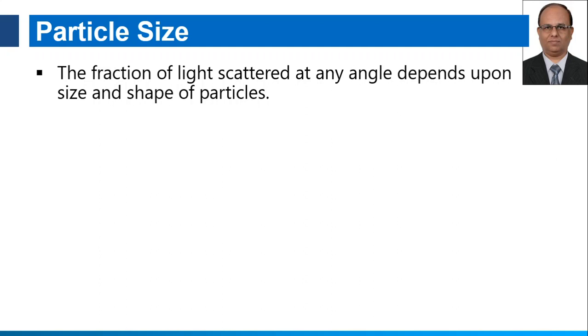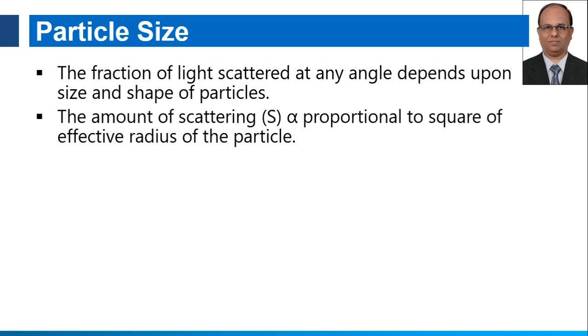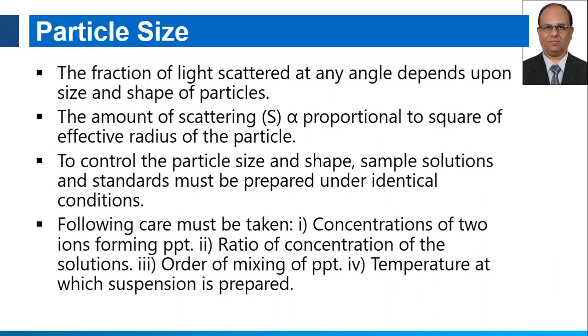The fraction of light scattered at any angle depends upon the size and shape of particles. The amount of scattering is directly proportional to the square of the effective radius of the particles. For control of particle size and shape, sample solutions and standards must be prepared under identical conditions — in the same laboratory with the same chemicals. We cannot use book values for comparison. Care must be taken that the concentration of the two ions forming the precipitate is properly controlled, and the ratio of concentrations is maintained properly. The most important factor is the order of mixing of the precipitate; whatever procedure is given for preparation, you have to follow the same procedure. Temperature at which the suspension is prepared will affect the particle size and definitively affect the measurements.